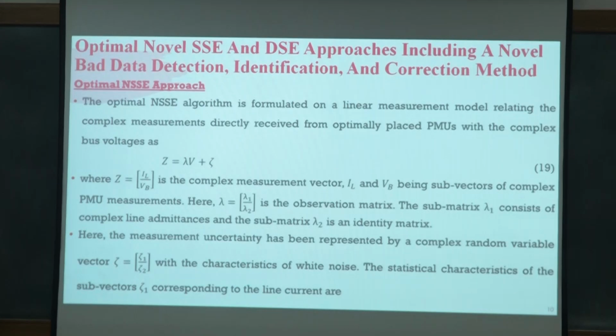Unfortunately, in certain cases the system may become unobservable, because the data being excluded contains some system information, and that information is lost. It may so happen we are unable to find the state vectors at some buses. But when this correction method is employed, the system always remains observable, because instead of excluding bad data we modify and correct it, so state estimation can continue with no scope for loss of observability.